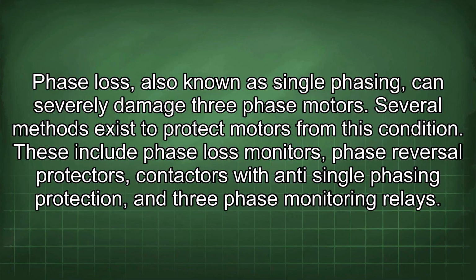Phase loss, also known as single phasing, can severely damage three-phase motors. Several methods exist to protect motors from this condition. These include phase loss monitors, phase reversal protectors, contactors with anti-single phasing protection, and three-phase monitoring relays.